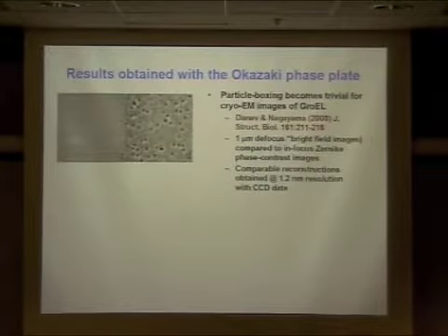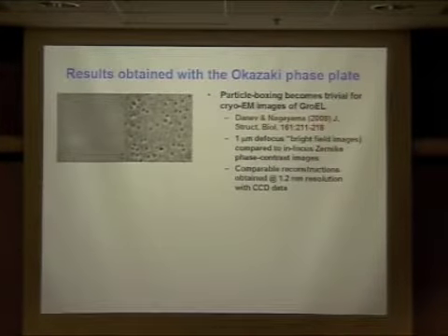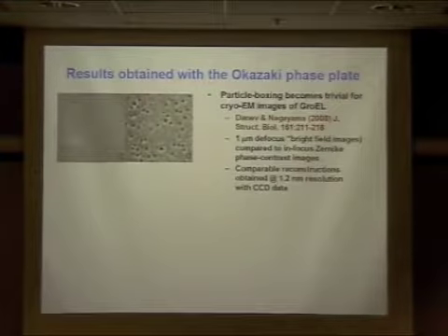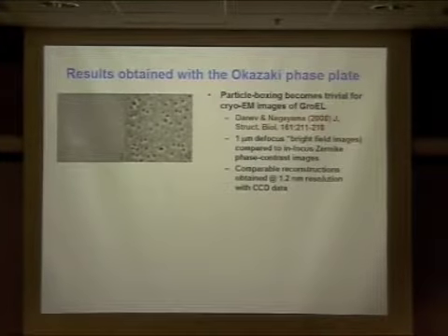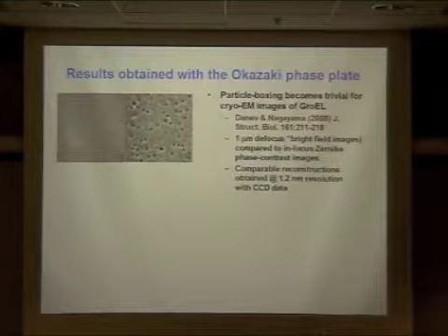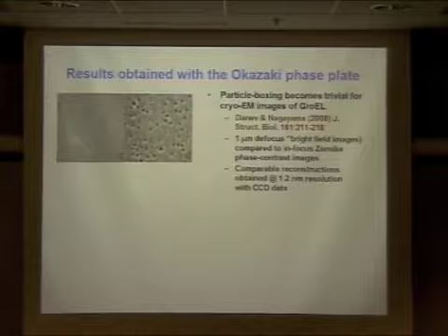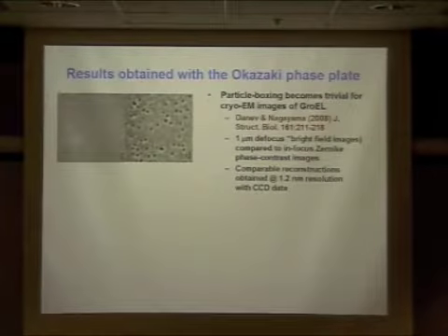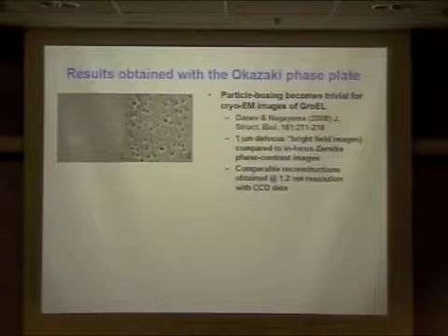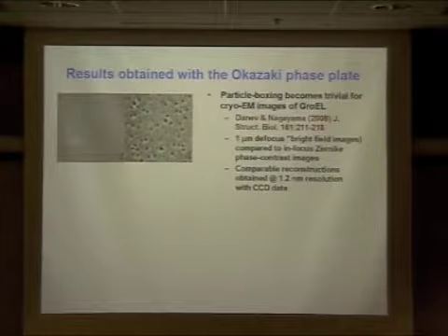Yeah. So the microscope that JEOL will sell you, I don't know all the details, but I do know the details of the one that's working in Okazaki right now. They also bought one of the ones that's being sold now. The one in Okazaki is a 3100, I think, and has a modified objective lens, so the focal length is 5 millimeters, and the pole piece isn't as long, and now the plane where the focal length of the objective lens is located is still accessible.